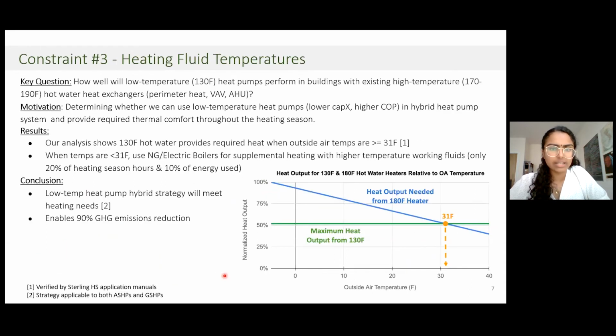Something else to consider is heating fluid temperatures. As we mentioned earlier, our existing heat exchangers run at between 170 and 190 degrees Fahrenheit. But our question was, could we use a lower heating fluid temperature in order to be able to use lower temperature heat pumps, which, as we mentioned, are lower capital and also higher efficiency. So what we found is that we can actually use 130-degree hot water when the outdoor air temperatures are roughly greater than 31 degrees Fahrenheit.